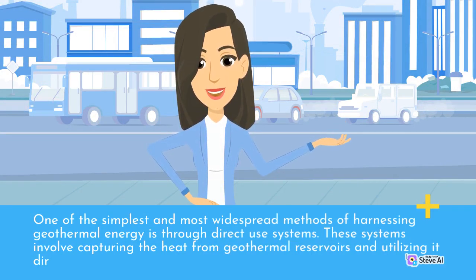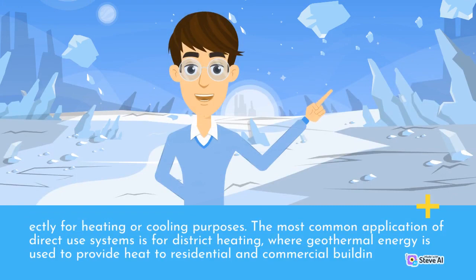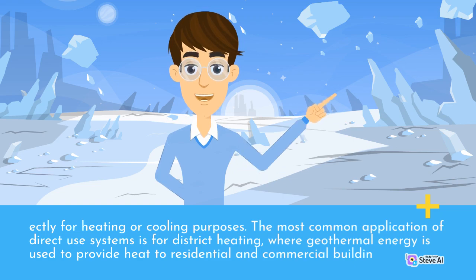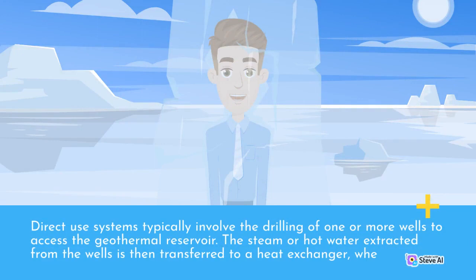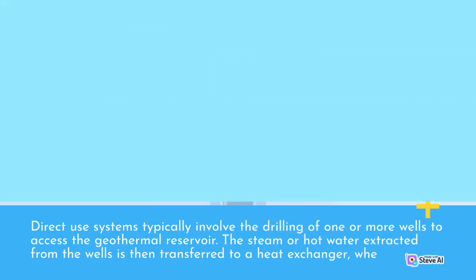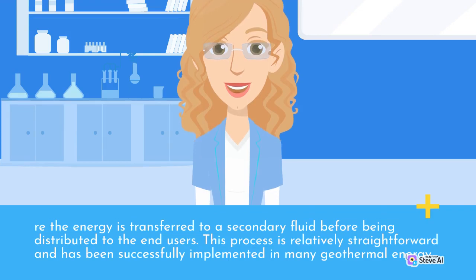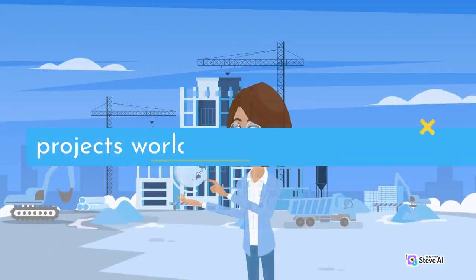These systems involve capturing the heat from geothermal reservoirs and utilizing it for heating or cooling purposes. The most common application of direct-use systems is for district heating, where geothermal energy is used to provide heat to residential and commercial buildings. Direct-use systems typically involve the drilling of one or more wells to access the geothermal reservoir. The steam or hot water extracted from the wells is then transferred to a heat exchanger, where the energy is transferred to a secondary fluid before being distributed to end-users. This process is relatively straightforward and has been successfully implemented in many geothermal energy projects worldwide.